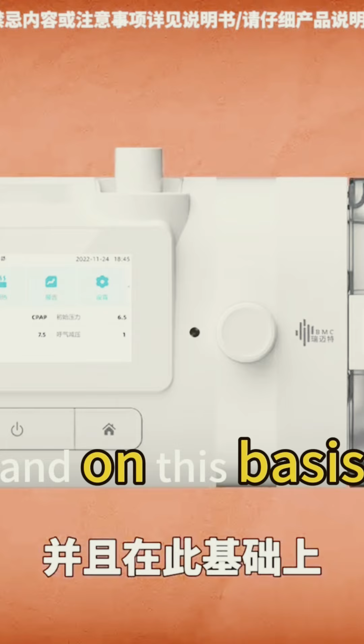For example, obstructive abnormalities require timely pressure rise. Central apnea requires avoiding pressure increase. The output of airflow should be consistent with the patient's breathing rhythm. If the response is sluggish or sudden, or the air flow output is unstable, it may affect the treatment effect, or even worsen it. A good home ventilator can use more intelligent algorithms to improve the quality of human-machine breathing and reduce discomfort during the initial wearing.